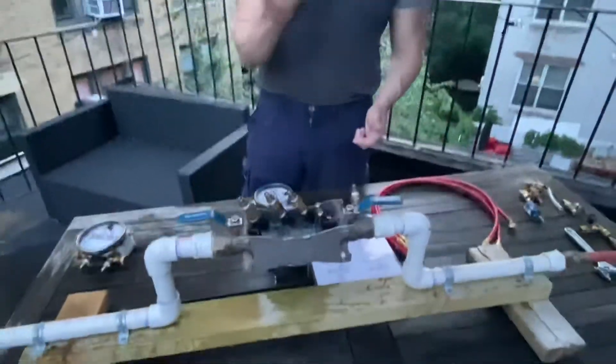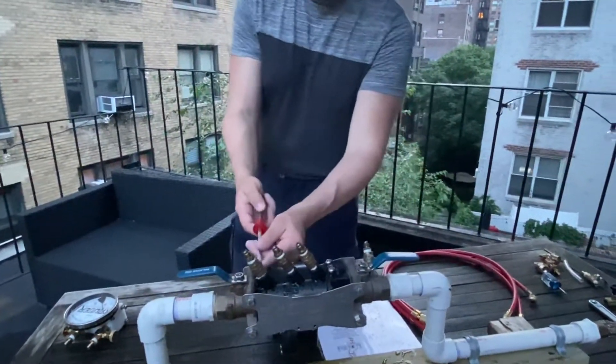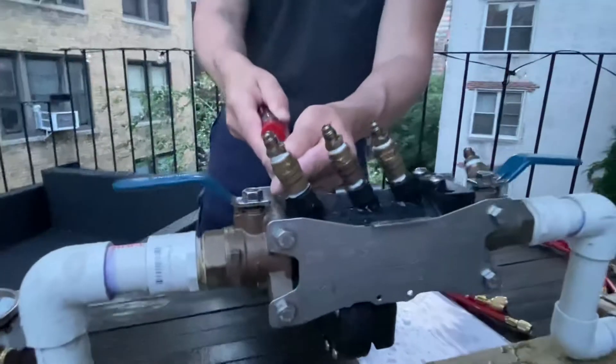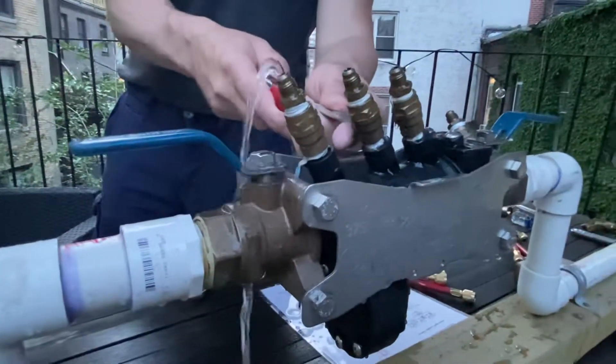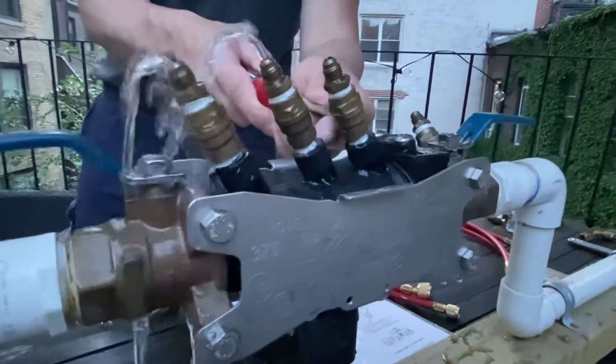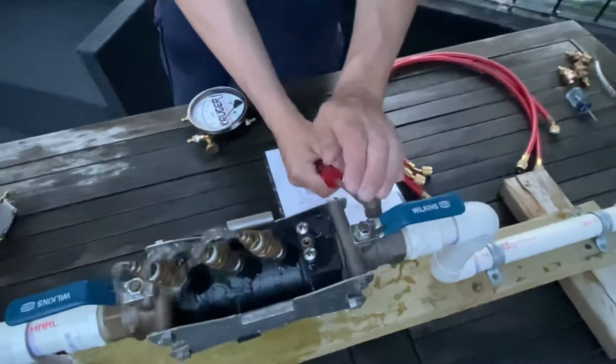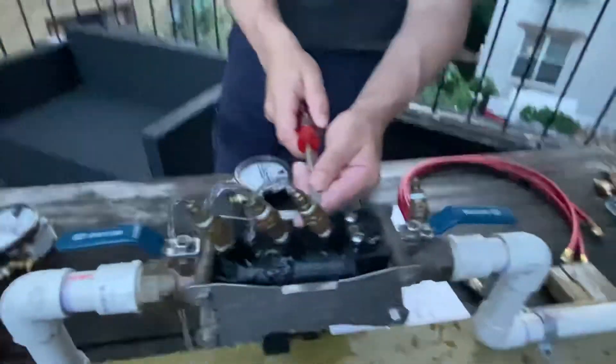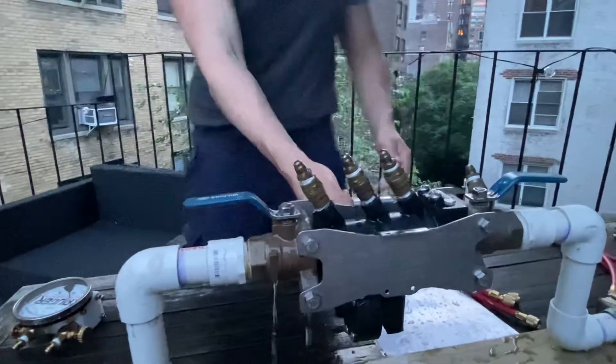We also have a flathead screwdriver to operate the test cocks. So you open test cock four first. The test is to flush the test cocks, so you open four, three, two, one, close one, two, three, four. You do that so you don't jump the relief valve prematurely.